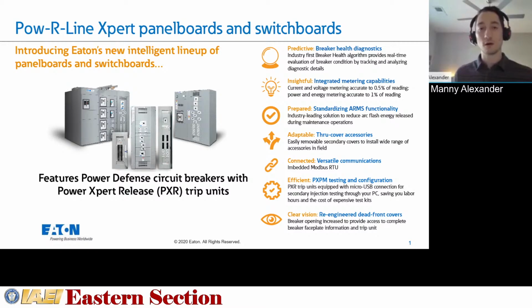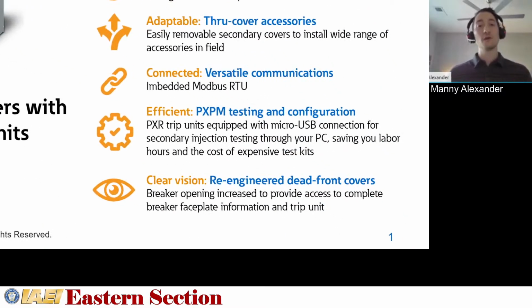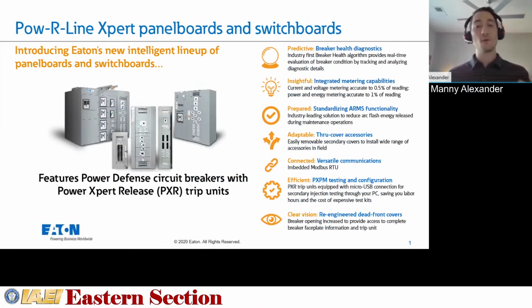And last on the screen are the re-engineered dead front covers. If you think about some of the dead front covers that are in the field today, the opening is only wide enough for that breaker handle to fit through. So if you needed access to confirm what that breaker is, maybe it's a spare in the field, or you needed to do a study down the road, you often want to verify the faceplate information on that breaker. So we've re-engineered the dead front covers to have a wider opening to give you that complete visibility to the breaker faceplate information. And now with the electronic trip units that have keypads and LCD screens, obviously it's easy access to those as well. Next slide, please, Tom.